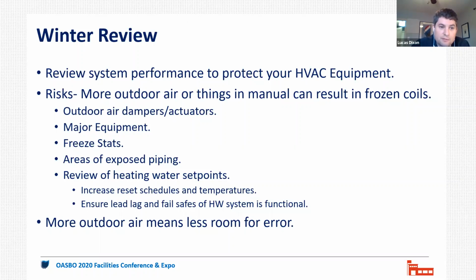We've also seen in building facilities managers, the areas of risk in your building where you've had either domestic water piping freeze or you've had fire suppression systems, if you have a water-based system, that have frozen. Consider that if you're bringing in more outdoor air and you are risking having colder air in your plenums or in your boiler rooms or other spaces, those areas that have experienced freezing in the past or you know are concerns, it's just going to amplify those risks. So pay special attention. Maybe it makes sense to add freeze tape or heat trace tape to these units or these areas preemptively to prevent an issue.